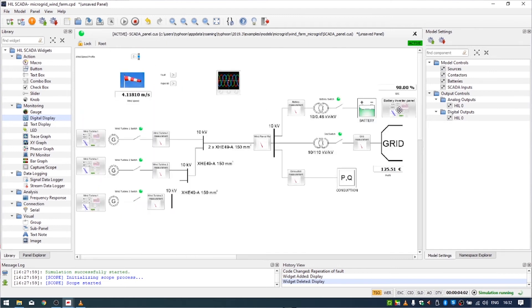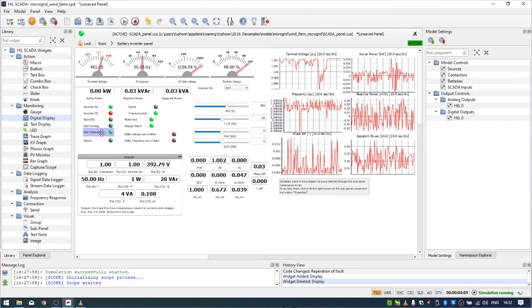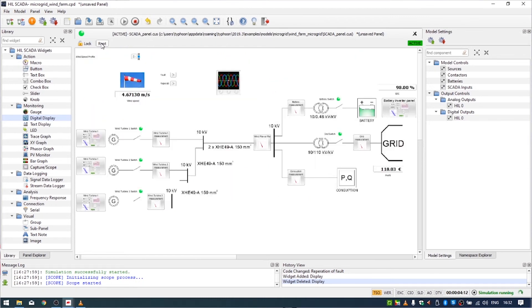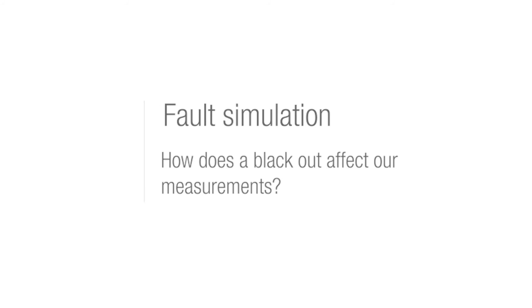There is also a battery inverter panel. We can see that we are currently working in grid-following mode, which means we are connected to the grid. We can also see the switch state. There is a fault button — we can simulate grid faults. In this case we simulate a blackout in the grid, and we will see how that affects our measurements.